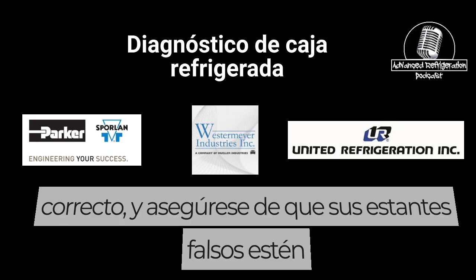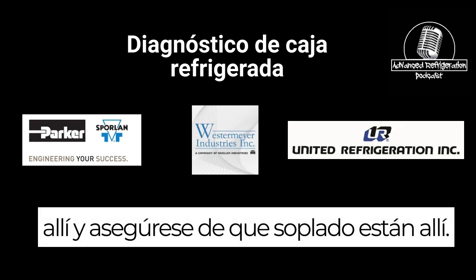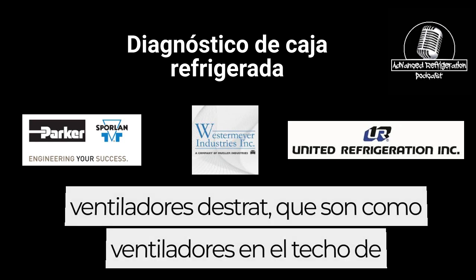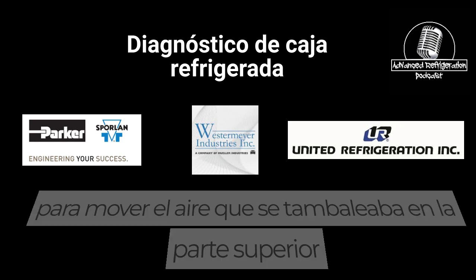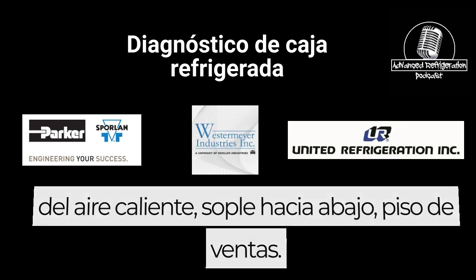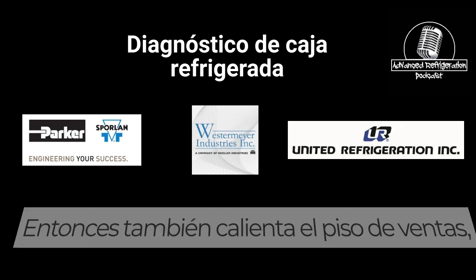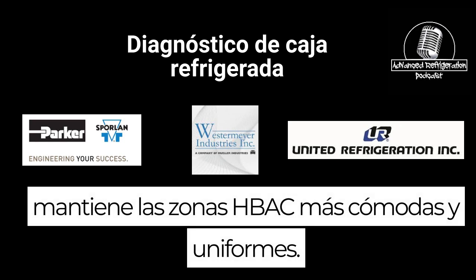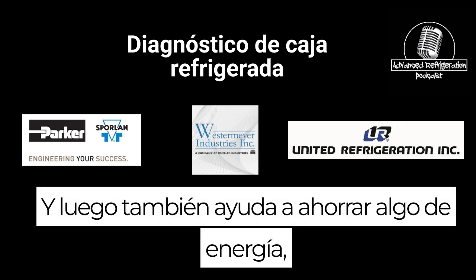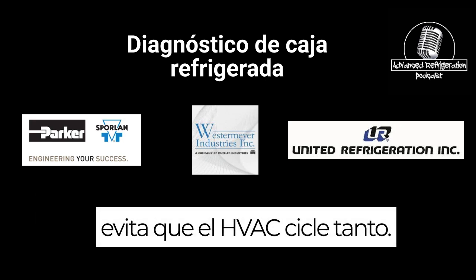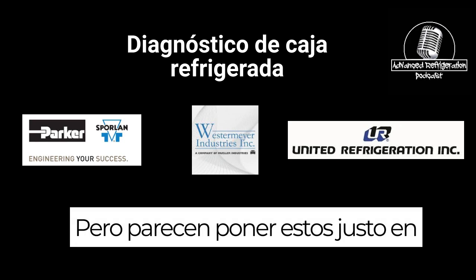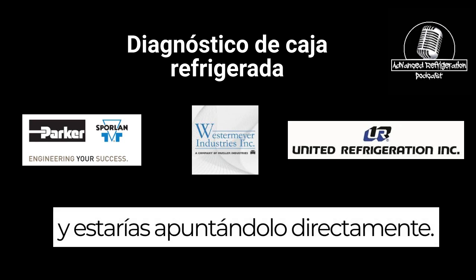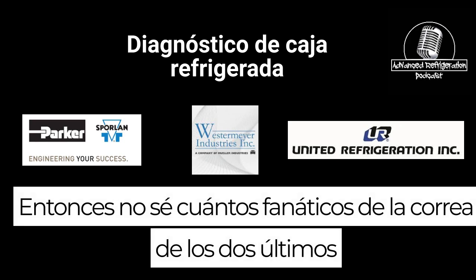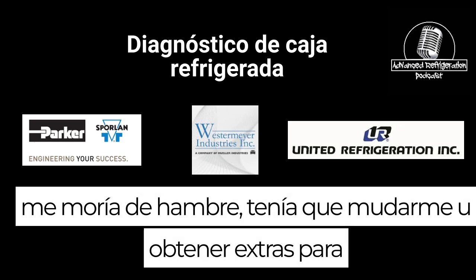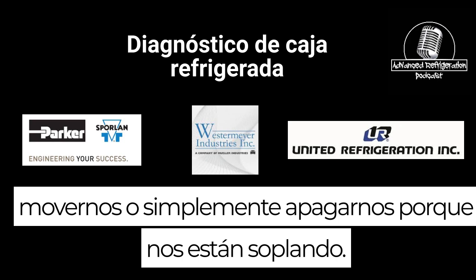Make sure you get all your specs right, make sure your false shelves are there, and make sure nothing's blowing in there. And I've been seeing a lot of destrat fans, which are fans up high by the ceiling to move around the stagnant air at the top and blow the warm air down onto the sales floor. So it also warms the sales floor up, keeps HVAC zones more comfortable and more even, and helps save some energy by keeping the HVAC from cycling so much. But they seem to put these right in front of every multi-deck case they can find, usually pointing right at it. I don't know how many destrat fans at the last two startups I did I had to either move, get extras for, or just turn off because they're blowing into cases.